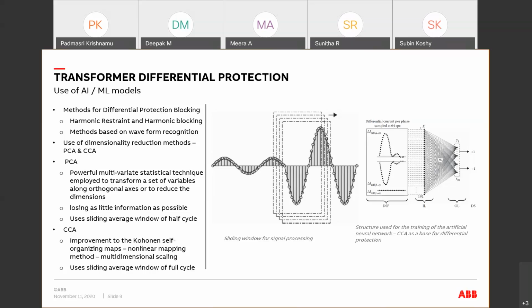So the PCA extracts the characteristic features from the transformer differential current waveform during distinct scenarios. During the various scenarios, these features allow us to classify the current signal as inrush, transient, or short circuit inside the power transformer. So PCA is one method, and the other method is CCA, that is the curvilinear component analysis, where the CCA is implemented as a self-organizing one-layer neural network.